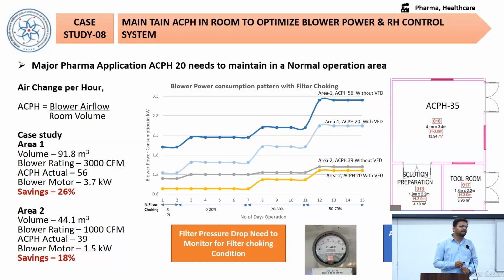As well, this is a specific case of pharma where 3 rooms are connected. A single AHU supplies the air to all 3 rooms. All 3 rooms need to be maintained at the same ACPH. Otherwise, if the DP level is different between the rooms, a small room may feel some starvation in the air supply and another room may have excess air. So that is a critical case to maintain ACPH in the pharma unit. We implemented these savings, and suggested a normal monitoring system to monitor the choking level of the filters.